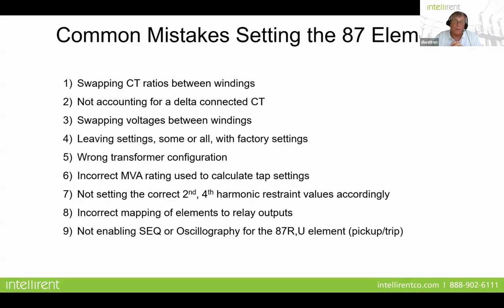Wrong transformer configuration. If you try and configure a DY11 on a DY1, you're going to have a mismatch in the phase angles, and that's going to cause the differential to nuisance trip on you. Incorrect MVA ratings used to calculate the tap settings, not setting the correct second and fourth harmonic restraint values accordingly, and making sure they're energized.